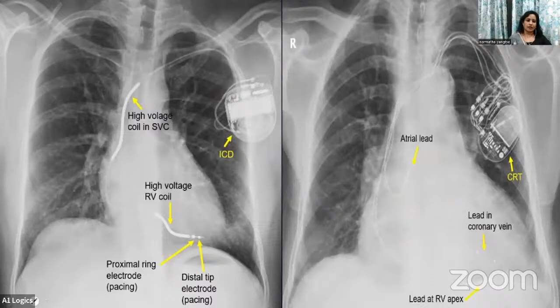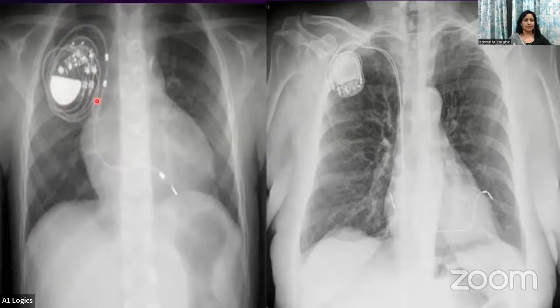For example, if you're seeing an X-ray like this, you can see this pulse generator is surrounded by multiple coilings of the lead. Actually, initially within a month of implantation or within 6 months, there are certain syndromes. The leads can get coiled around, so the lead gets retracted, and it can cause stimulation of the phrenic nerve, diaphragmatic stimulation. So the patient will have symptoms like hiccups, recurrent hiccups, or if there is any stimulation of the brachial plexus, the patient can have impulses in the arm. This is called Twiddler's syndrome. So you have to ask about the symptoms also, and you should be very careful if the patient tells these symptoms.